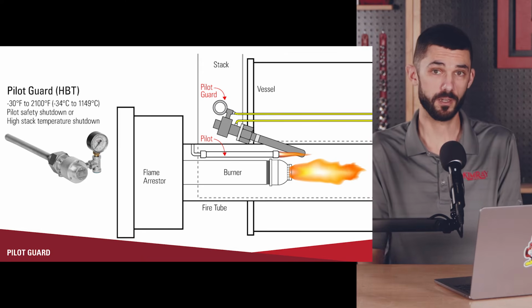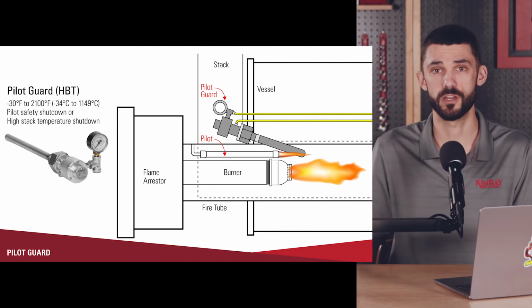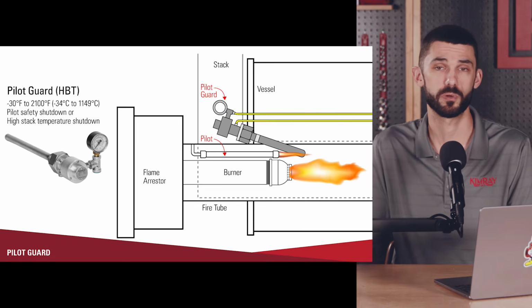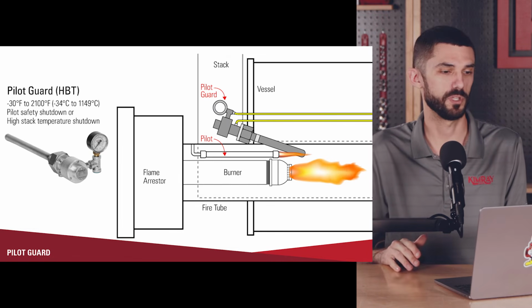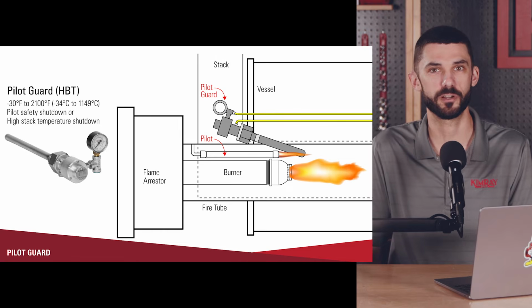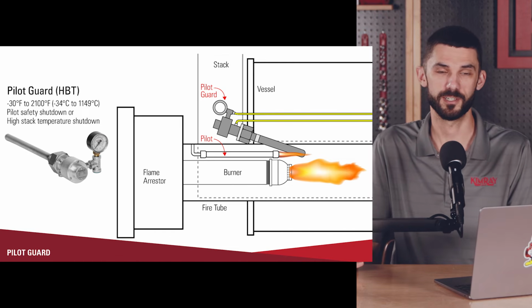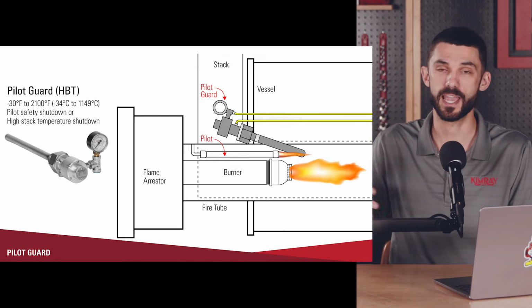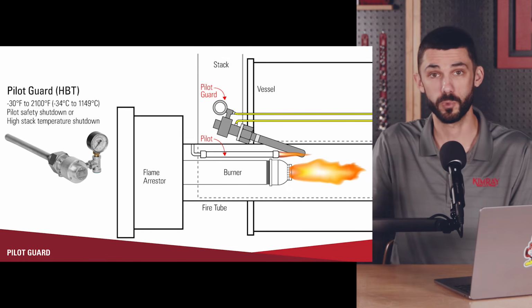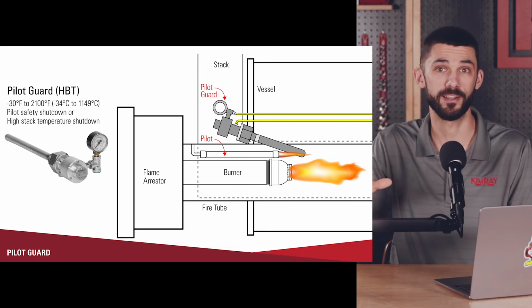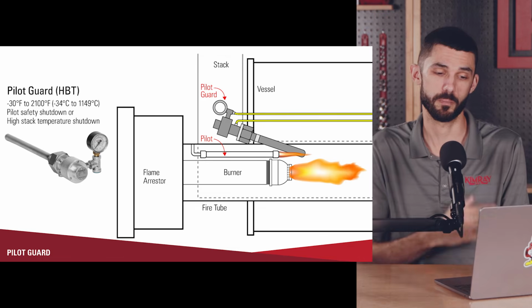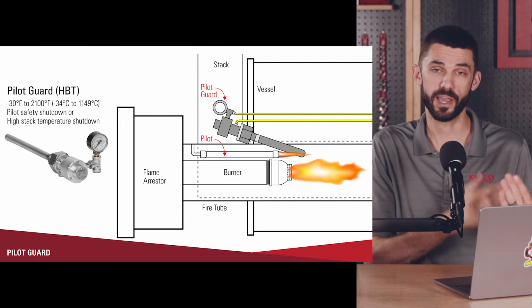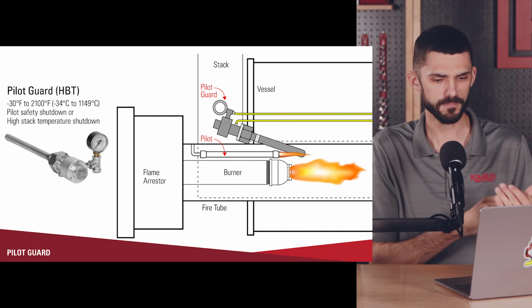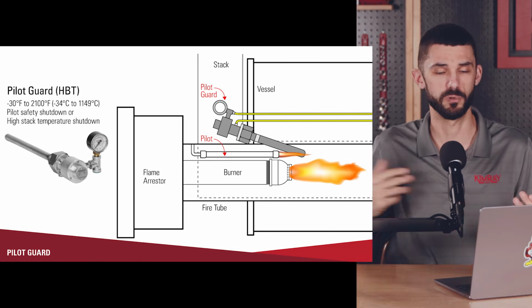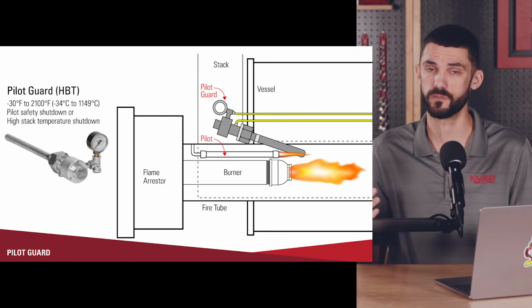I mentioned before the pilot guard. The pilot guard is just there to monitor the pilot flame to make sure it's present. It's really similar to what your hot water heater has at your house. If it's a gas heated hot water heater, you're going to have a thermocouple that is making sure that there's a pilot flame present. The pilot guard is doing the exact same thing. The probe will be directly in the pilot flame, monitoring that, and it will make sure that that's present before it lets supply gas through to the rest of the system.